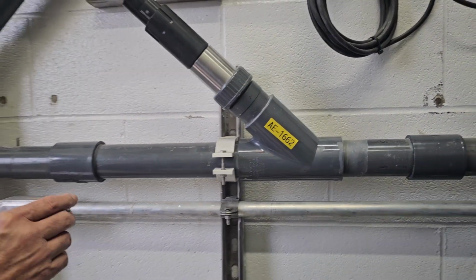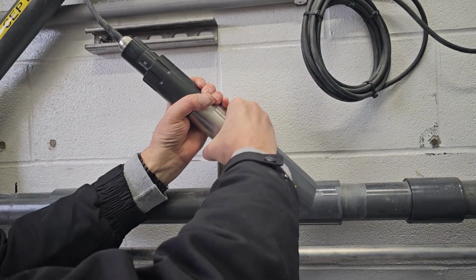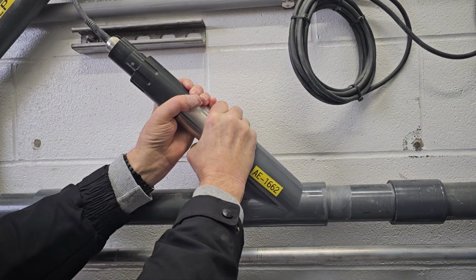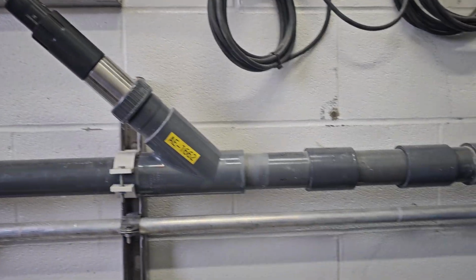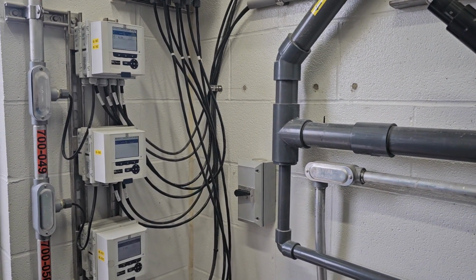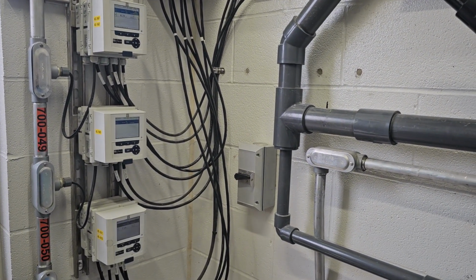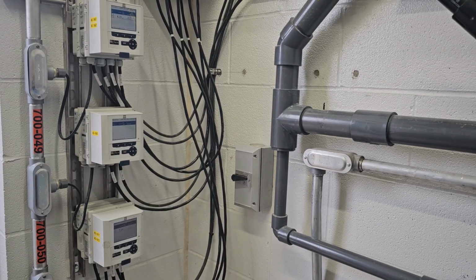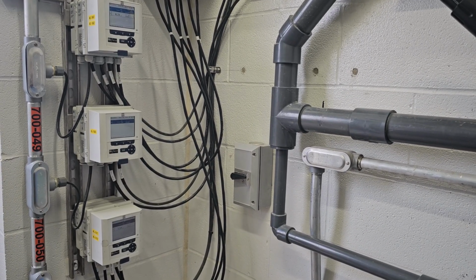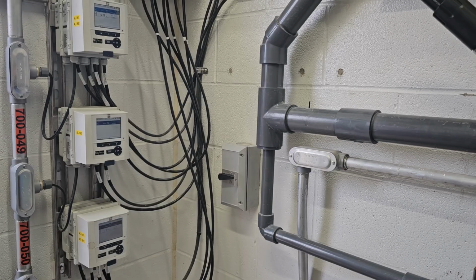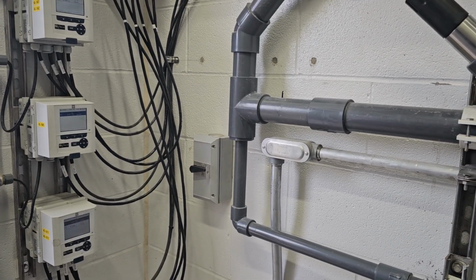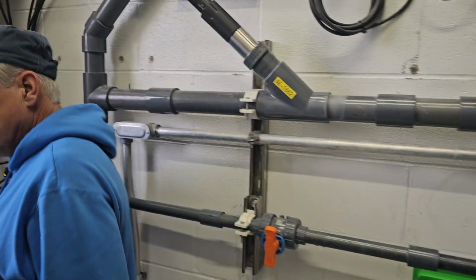You've got to make sure these are pretty tight. It's probably also a good idea once you guys start running things through here to come in and check in case something needs hand tightening. During first startup last year there were a number of things leaking, and Barry just came in and gave them another turn. So since you've done maintenance, pulling them out and checking on them, it's a good idea to come in here anytime you start up this building and check for leaks.